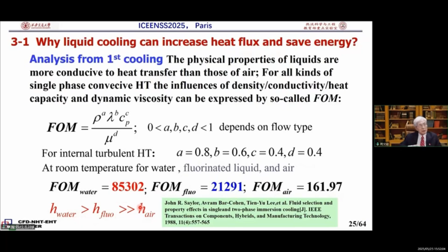And this is for convective heat transfer in the tube. For water, this is 85,000. For fluorinate, it's 21,000, but for air, it's only 161. Therefore, the heat transfer coefficient of water and fluorinate is much higher than air cooling. Because of the high heat transfer coefficient, the required flow rate of liquid is much less than that of air. Therefore, the pumping power of liquid is much less than the pumping power of air.